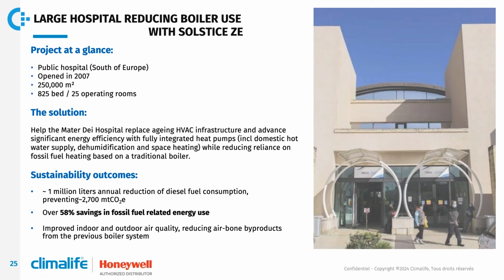As a result of this technical solution based on ultra-low GWP R1234ze, there was a reduction of diesel fuel consumption by 1 million liters per year, meaning that we save more than 2,700 metric tons of CO2 equivalent, or in other words, 58% saving in fossil fuel related energy use, for example using a boiler. On top of that, we also improve the indoor and outdoor air quality for this use.